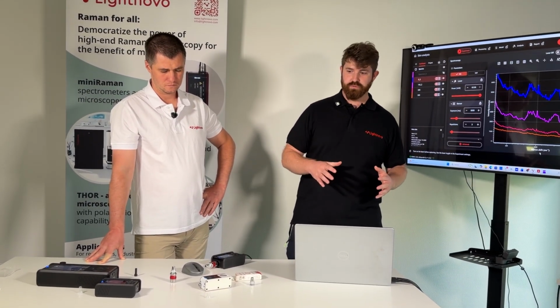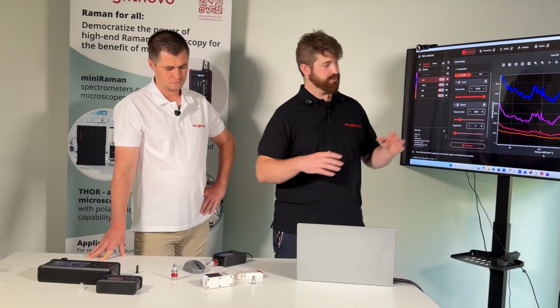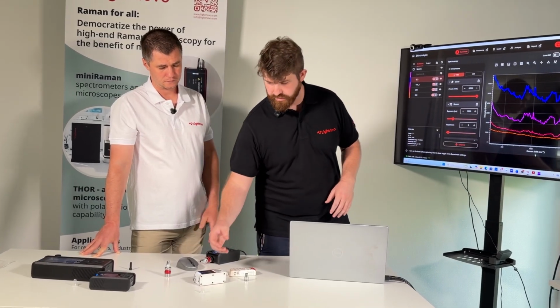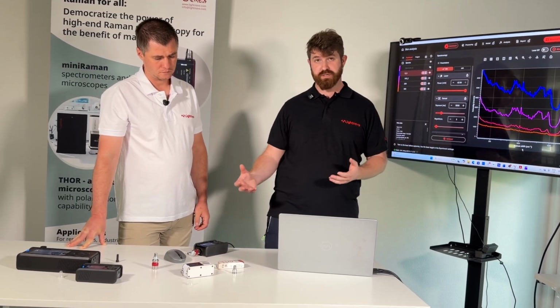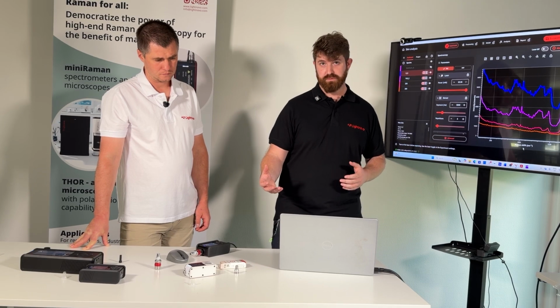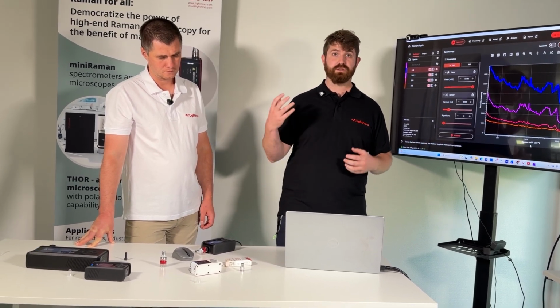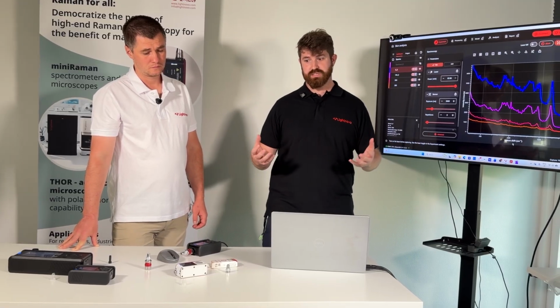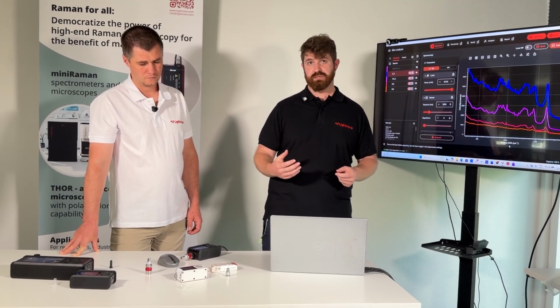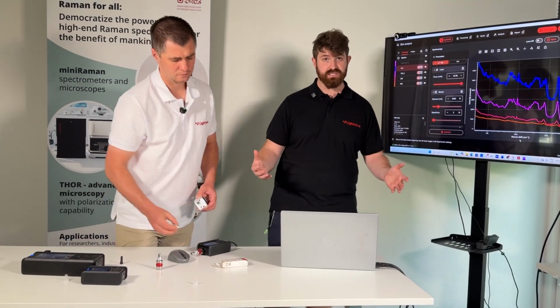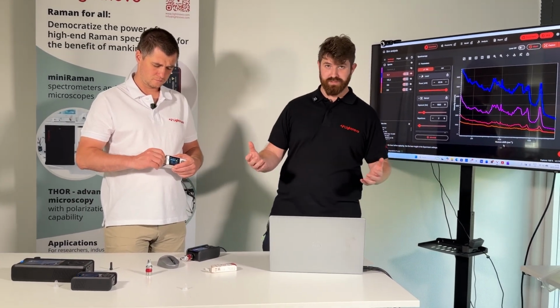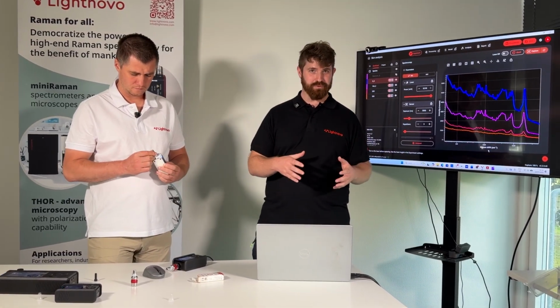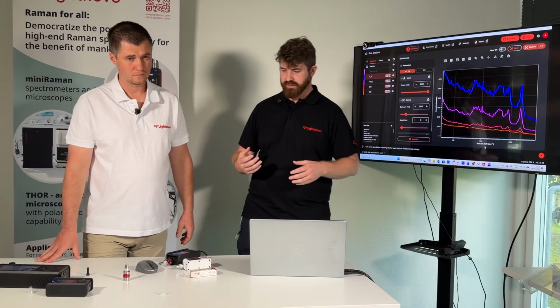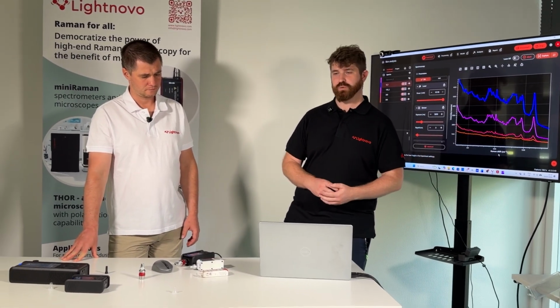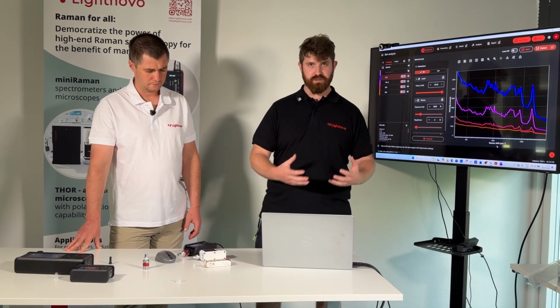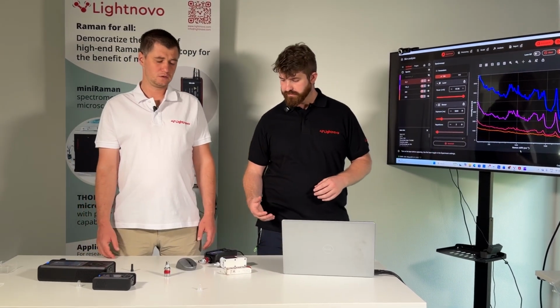So the last part that we're going to move on to is going to move away from the screen, or at least from this big screen and our MiraSpec Flow software, and it's going to be an actual onboard chemometrics that we've put onto the miniRaman to specifically look at things like the lipids and the water that you see in skin. And so for that, we need to have a 660 nanometer wavelength, so we have that extended range so that we can actually see the peaks that are of relevance. Does mean that we lose the information from all of the fingerprint region, because the fluorescence is so large that even with my skin, which is not very fluorescent at all, you still have a lot of problems seeing that fingerprint information.